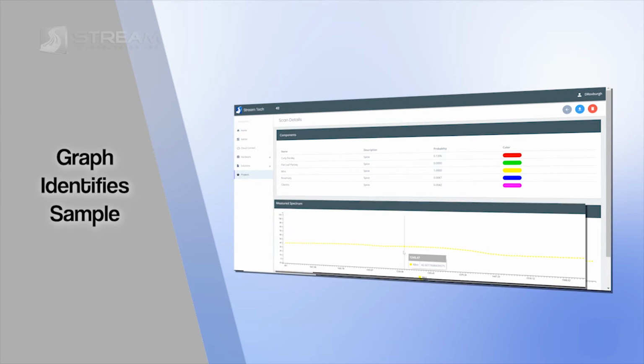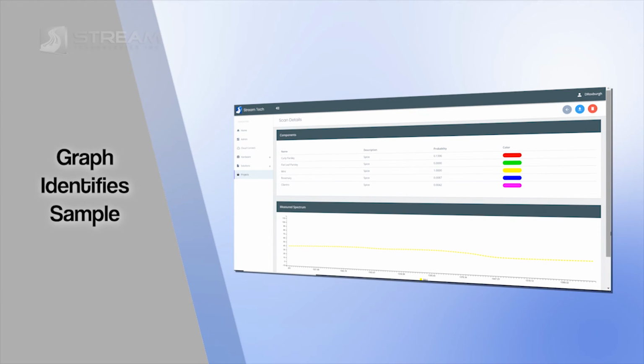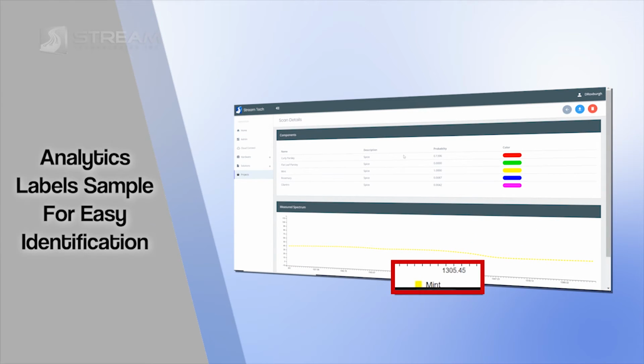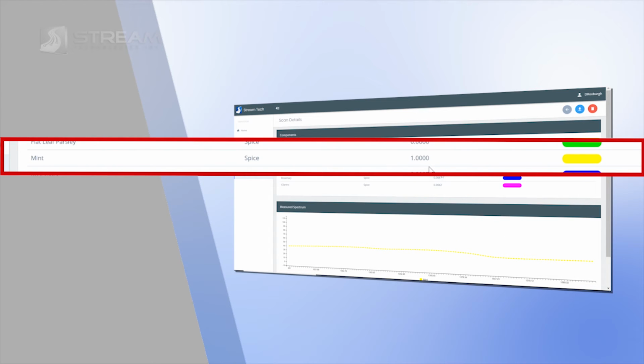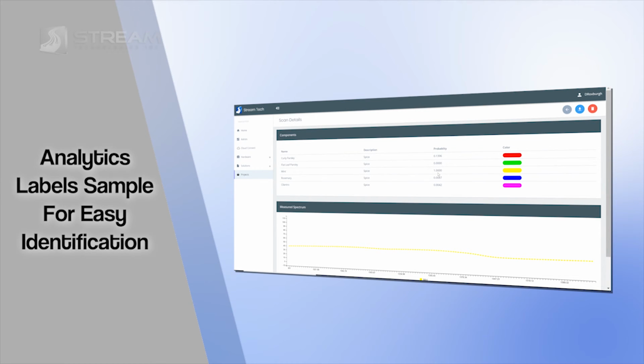Here we'll see a plot showing the spectral scan that we just took. It's been colored to match the component that it identified as, which in this case is mint, and we set that to be yellow when we set up our solution. And then up here on the components, it's looking for the components we trained on inside of that sample, and it's telling us how sure it is that it's found that component in the sample. And we can look here and see mint. It has decided it's mint with pretty much 100% probability, so that's a pretty good identification there. It basically labels the graph with the color, which is mint, and also a label saying that the scan is a mint.